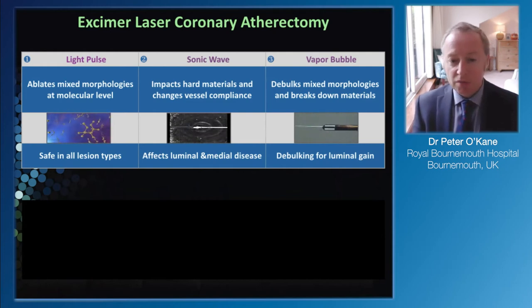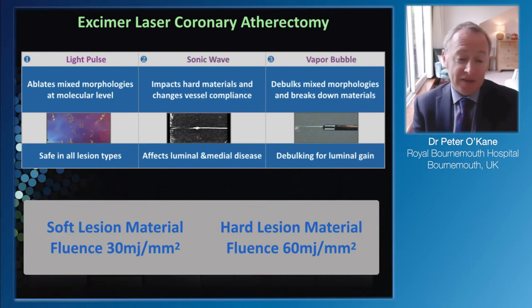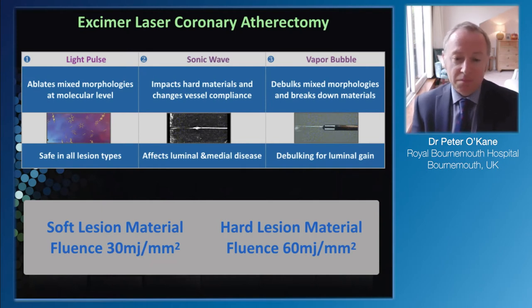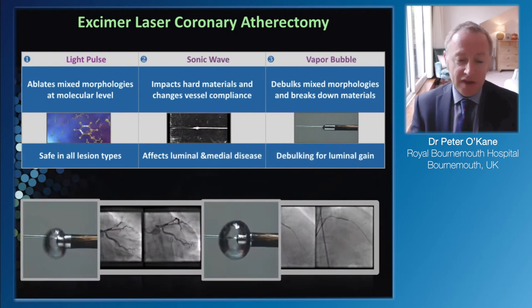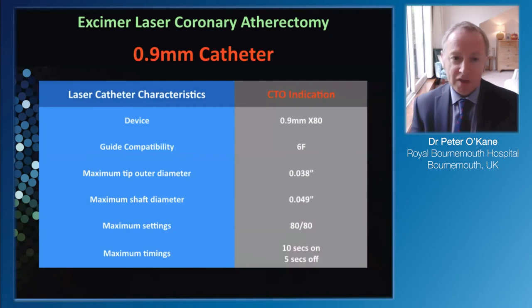We have adjustment on the amount of energy we can deliver - two types. First, there's the fluence, which is the amount of energy delivered at the catheter tip, measured in millijoules per millimetre squared. Then there's the frequency in hertz, which we can also influence. When we want to go through harder tissue, we increase the hertz for more penetration. When dealing with soft tissue like thrombus in an LAD, we just need low fluence. With a more resistant plaque we need higher fluence, and the diameter of the vapour bubble is greater at higher fluence.